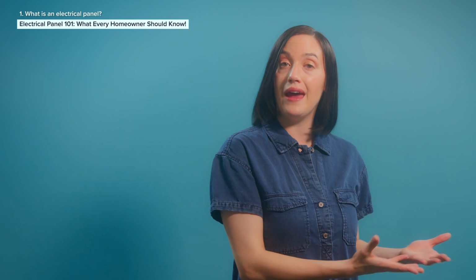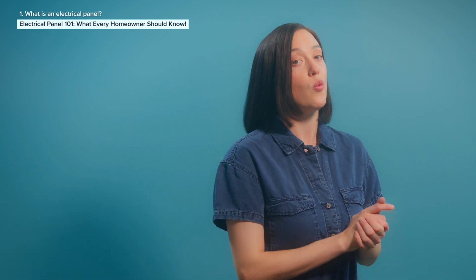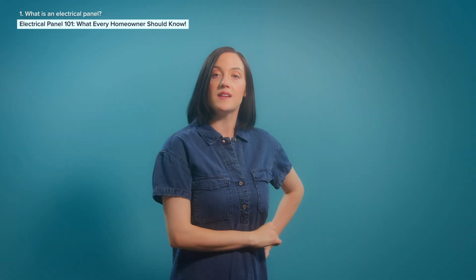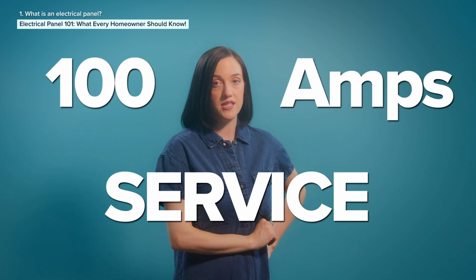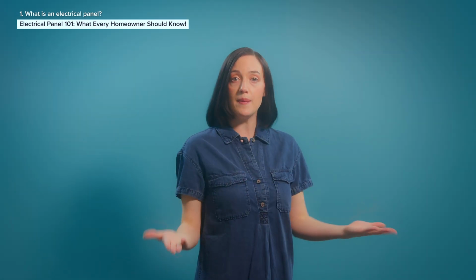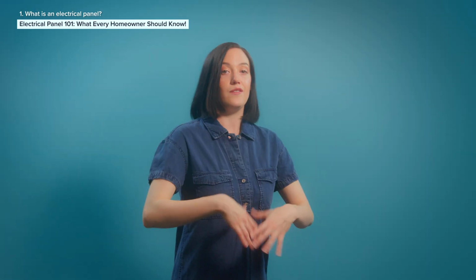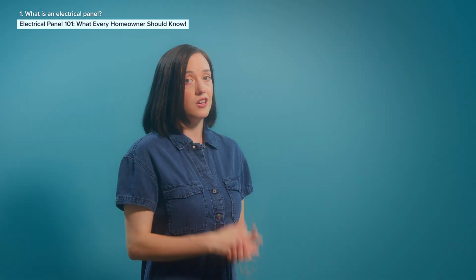The total amount of power your electrical panel can supply is limited by your home's electrical service. Your panel tells you the strength of your electrical service, measured in amps. Most homes in Canada have at least 100 amp service. In fact, they need to. According to most building codes, big homes often need 200 amp service. If your service isn't strong enough, your electrical system will be overloaded, meaning potential overheating and maybe even electrical fires. In fact, if you don't have at least 100 amp service, you might have a hard time finding home insurance. But more on that later.